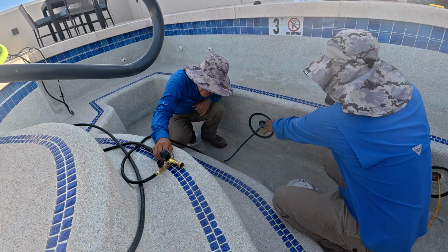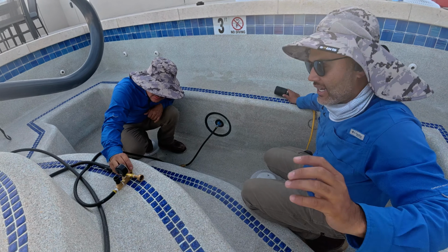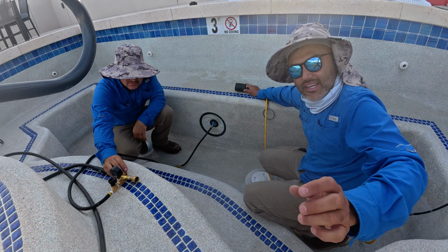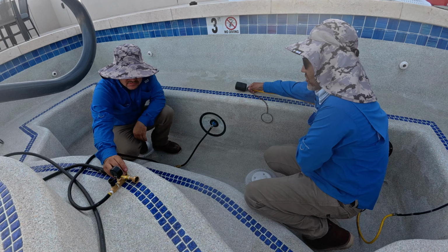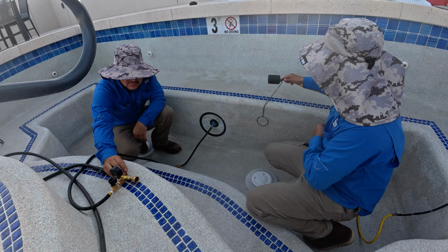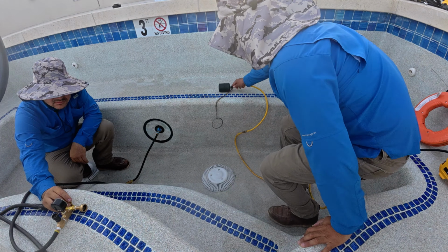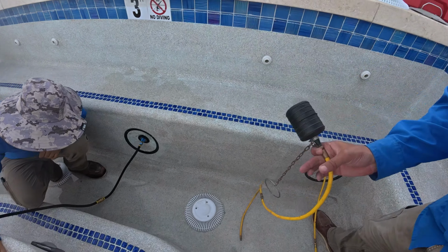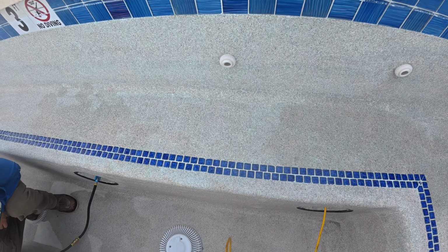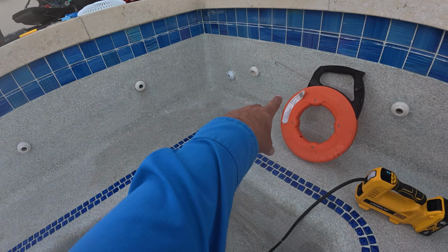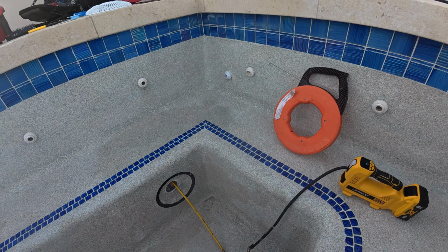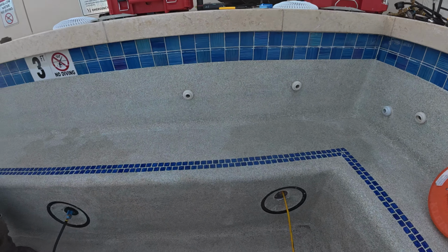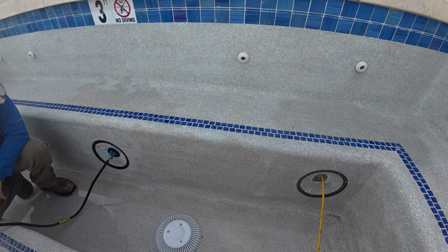At the moment, we can go ahead and test it section for section. So for example, we can test this section here. After we test it and it holds pressure, then we can bring our plug 6 inches back, up to here, and then another 6 inches back, until we can test the whole line that failed. And past this wall below, we can physically see the pipe. We'll take you on a tour downstairs right now.